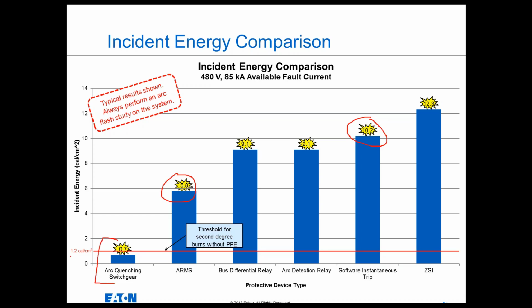but then our quenching switchgear comes in at 0.7. So well below that 1.2 calorie per centimeter squared threshold for which you'll get second degree burns if you're not wearing any PPE, which, you know, shame on you if you're not. But so 0.7, so again, one or two orders of magnitude lower than what has typically been available to us for reducing incident energy. So pretty dramatic reduction. And it's that extremely low incident energy that allows the switchgear to survive an arc flash event without being damaged, and allows it to be brought back online much faster to get those critical processes running again.